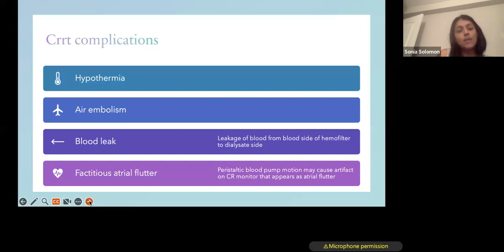The other risk is air embolism. If air gets into the circuit and goes back to the patient, that can definitely lead to issues. You can also have a blood leak, where the blood from one side of the filter and the dialysate from the other side of the filter, there's a break in the system and it causes them to mix. And then the other thing you want to look for is atrial flutter. Sometimes the pump motion can cause an artifact on the screen and give you this atrial flutter while they're on CRRT.